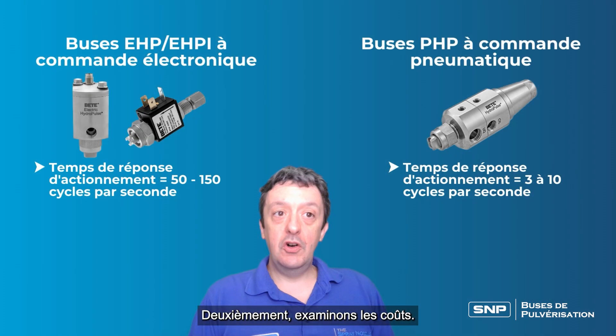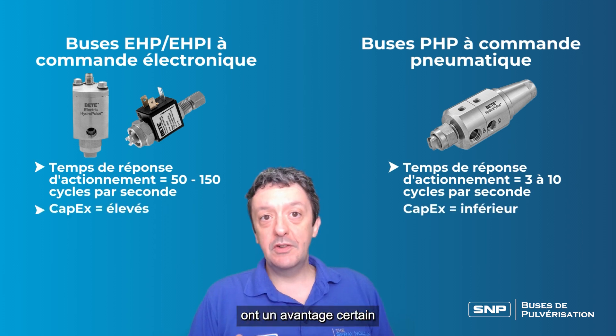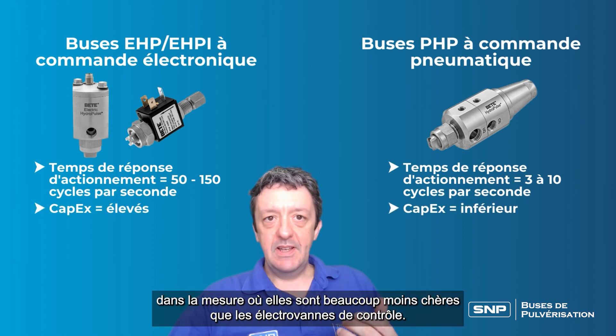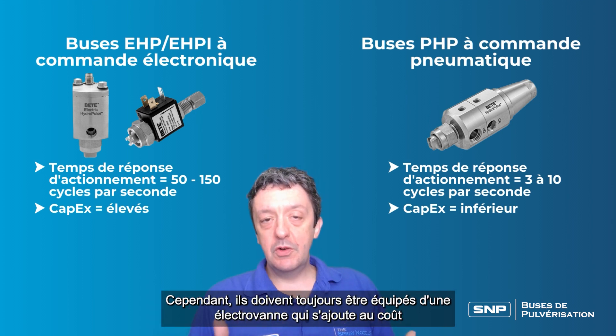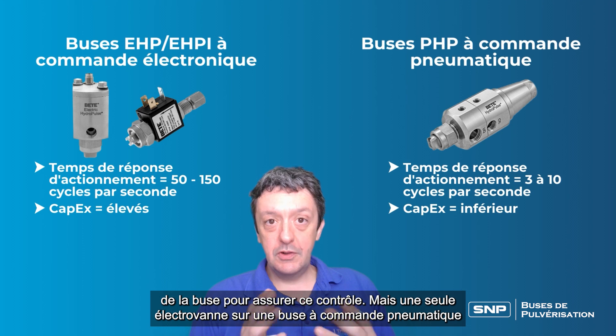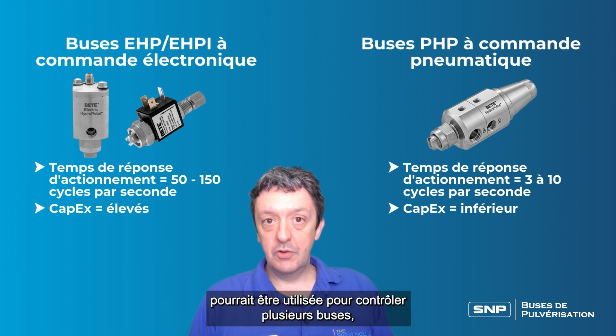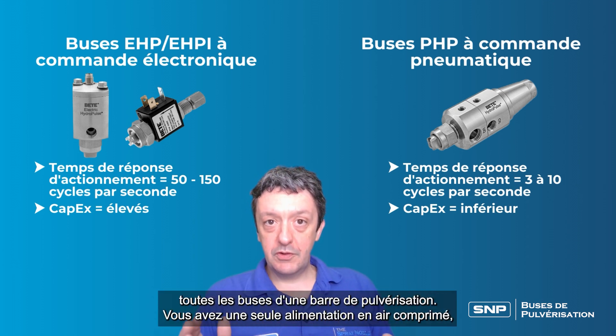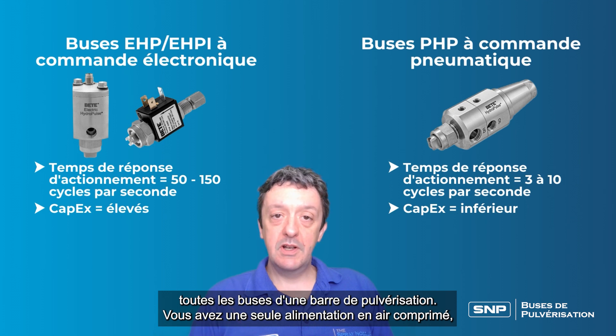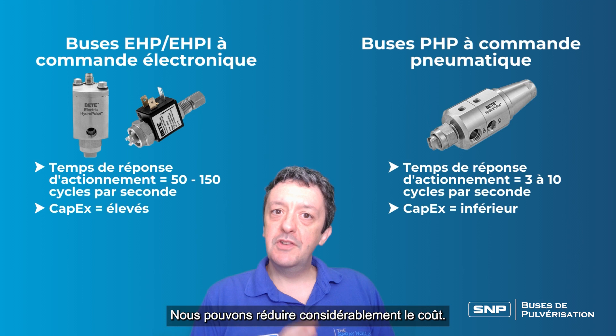Secondly, let's look at cost. The PHP air actuated nozzles have a distinctive advantage — they are a lot cheaper than the solenoid-controlled valves. However, they still need a solenoid valve added to the cost of the nozzle, but a single solenoid valve on air actuated nozzles can be used to control multiple nozzles. So the cost of those solenoids can be spread out over all the nozzles on a spray bar, with one actuating air supply controlled by a single solenoid, bringing the cost down considerably.